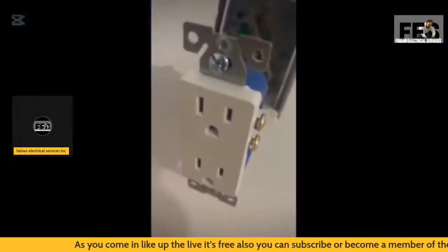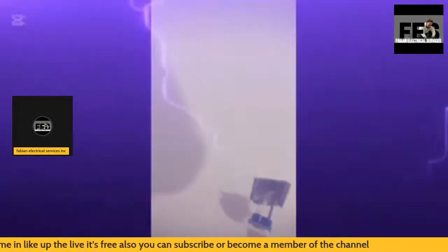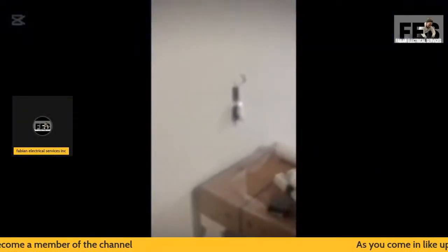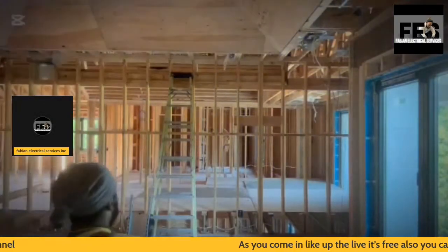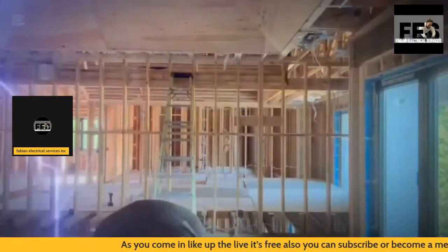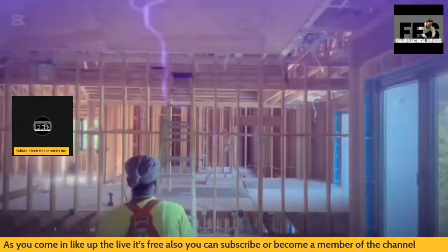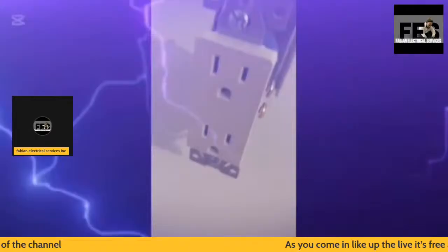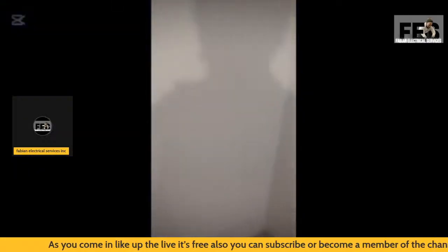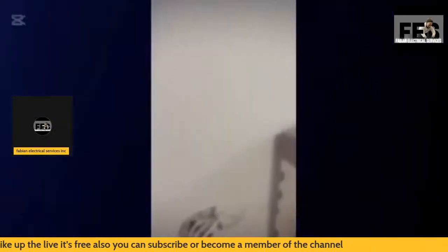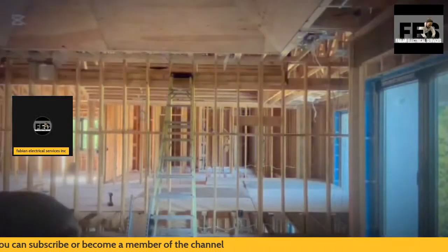Again, it's only used for plugins, and you saw how I just did it. I plugged it into the receptacle, which is live, and I go to the panel. This tester is great because you can stay at a distance and hear the beep, which lets you know the electrical circuit is pretty much off. Once you hear that beep, you know it's dead - there's nothing there. That's basically how I troubleshoot my receptacles on a daily basis with this tester.